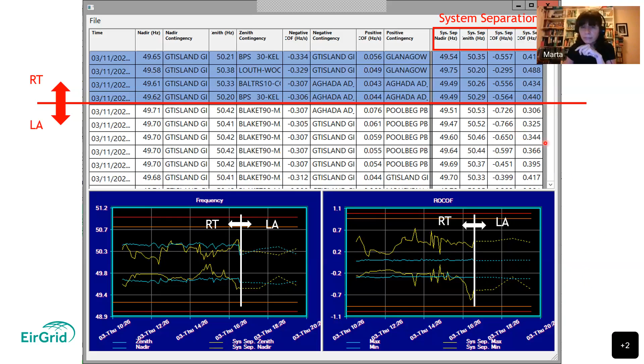We have two sub-screens. One is for all contingencies except for system separation, which is the most critical contingency for us because we only have one tie line between north and south. So it was considered important to separate this contingency on its own and produce the results in graphical format. We have the limits, the amber alert and the red alert, and if we exceed those limits, the table will show us with the color in orange or in red as well.